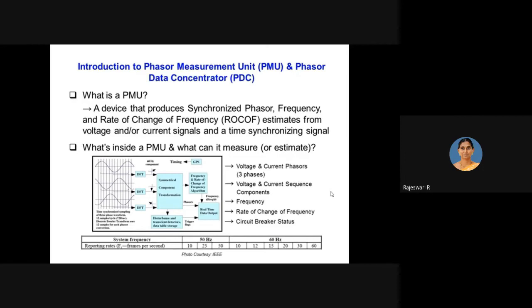The data acquired in a window, one cycle, may have a window length of cycle time 20 milliseconds. So for each 20 milliseconds, a number of samples are taken, and this one window or one cycle of data is fed as input to the processor, which converts it using DFT, a mathematical tool that converts the sequence of samples into phasor form.